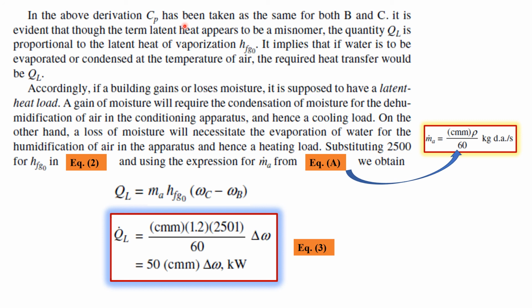would be QL. Accordingly, if a building gains or loses moisture, it is supposed to have a latent heat gain. A gain of moisture will require the condensation of the moisture for the dehumidification of air in the air conditioning apparatus, and hence it imposes a cooling load on the air conditioning apparatus. On the other hand, if there is a building which is continuously losing moisture, it will basically require the evaporation of water for humidifying the space, and for that purpose ultimately a heating load is imposed on the air conditioning apparatus.